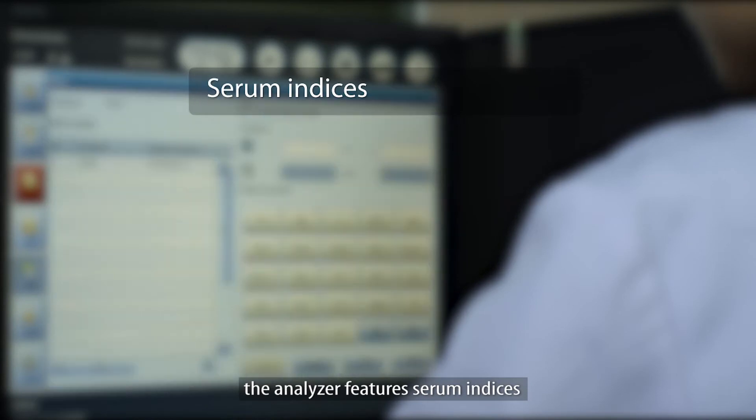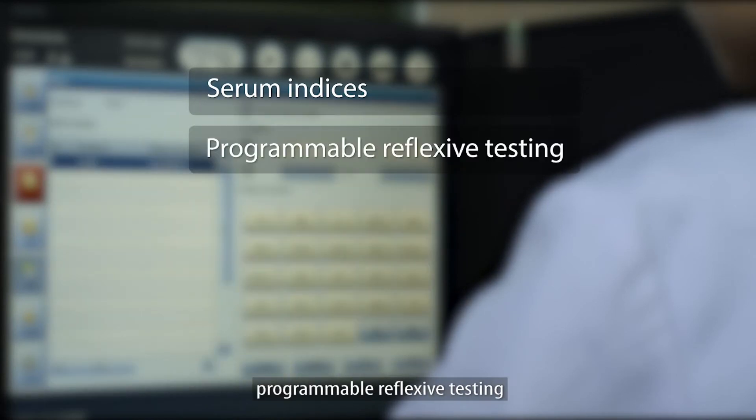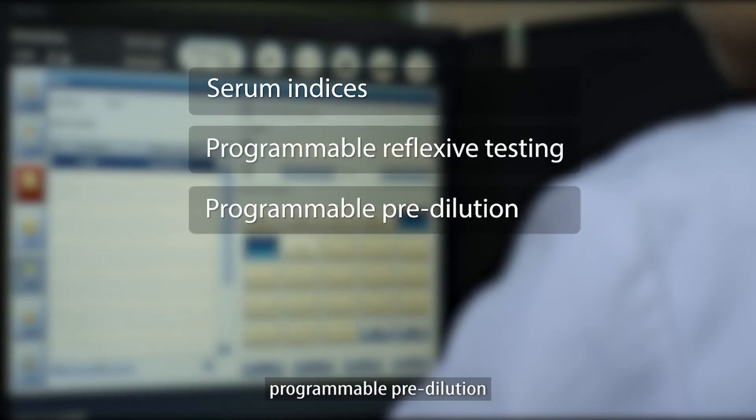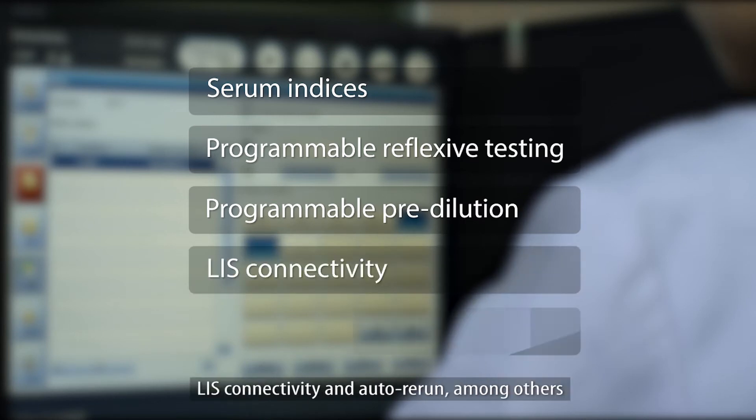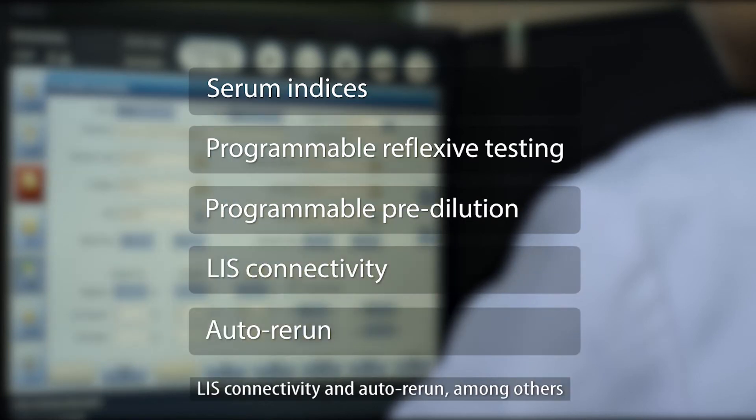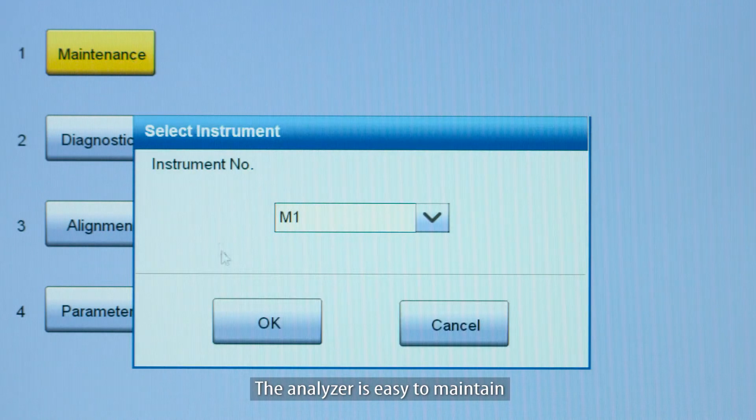For software, the analyzer features serum indices, programmable reflexive testing, programmable pre-dilution, LIS connectivity and auto-rerun among others.